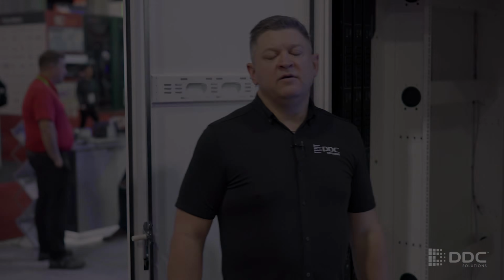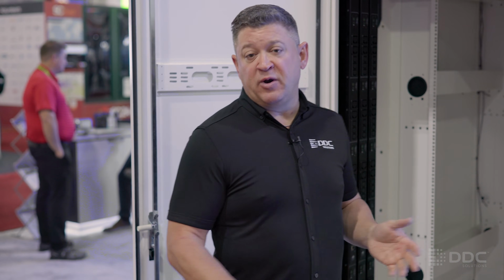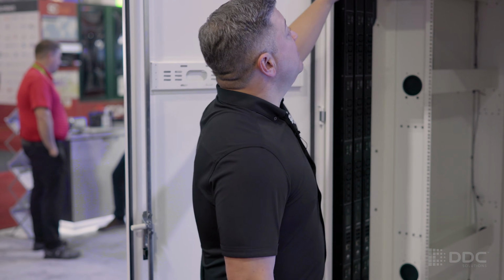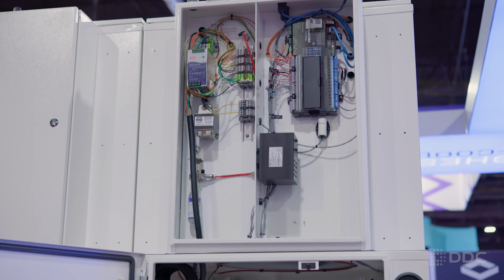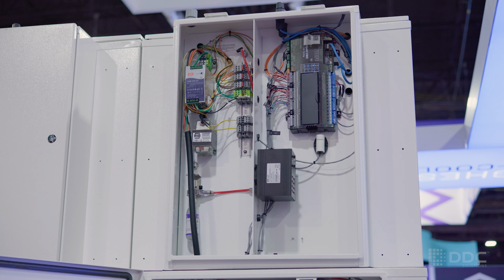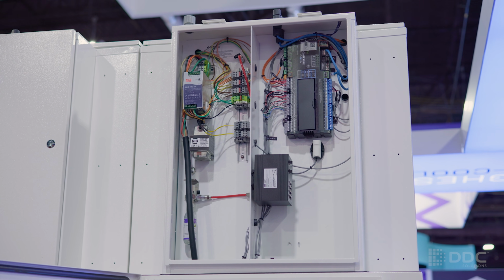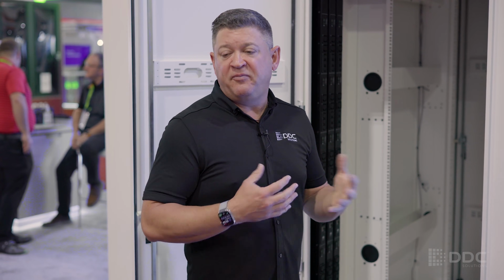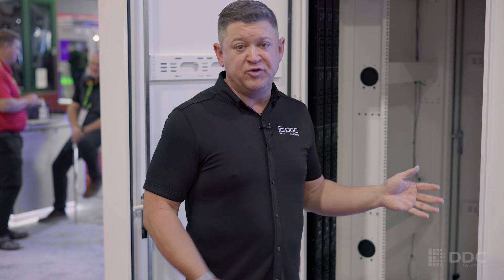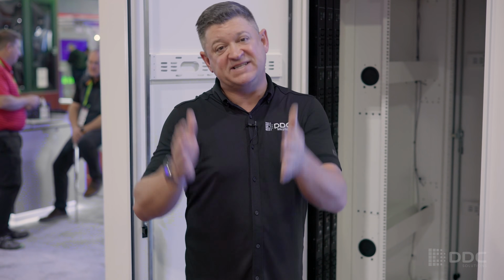From the rear of the cabinet, DDC S-Series cabinets have a variety of features we want to run through quickly. Up in the management box, we have our controller that provides intelligent data processing for all the sensors within the cabinet. It also contains the head unit for the in-cabinet fire suppression system—providing unbelievable protection, solving a fire problem at the cabinet level and reducing your risk and mitigation zone down to a single cabinet.